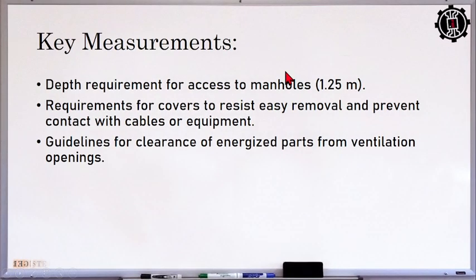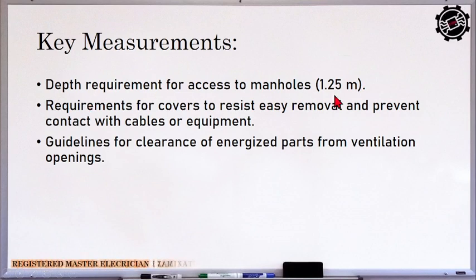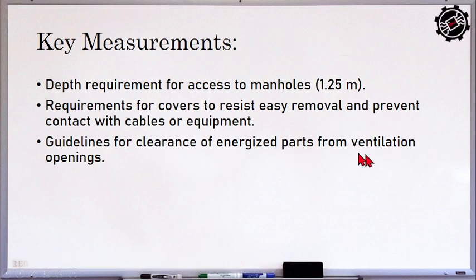So the measurements, so the depth requirement for manholes, that is no need na dapat meron ka ng ladder is 1.25 meters. So requirement for covers to resist easy removal and prevent contact with cables or equipment. The requirement is the covers cannot be removed without using the proper tools. Then guidelines for clearance of energized parts from ventilation opening. So dapat maglalagay ka ng baffles and louvers.